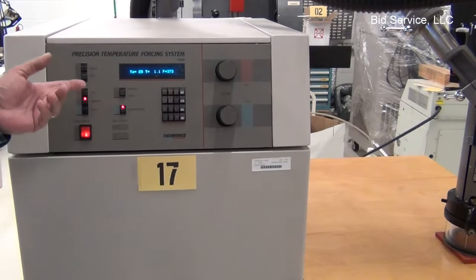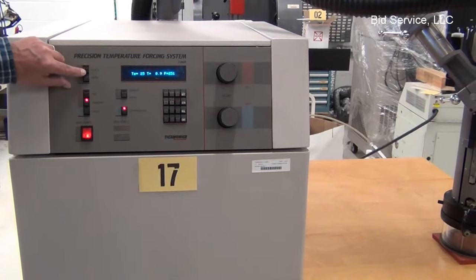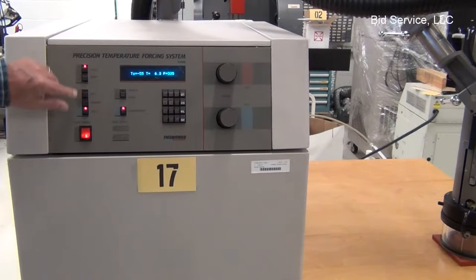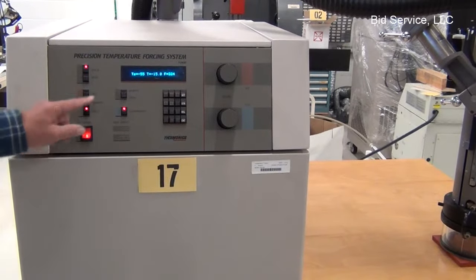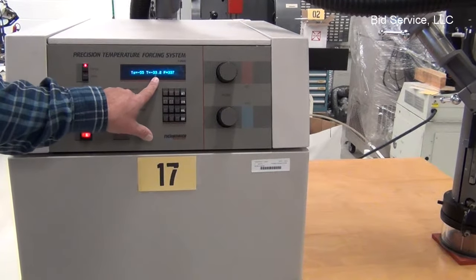To initiate the cycle sequence, once you've got it all programmed, just hit cycle. The cycle light comes on, it'll go down to the cold. And the set point here is minus fifty-five and you can watch the actual here.